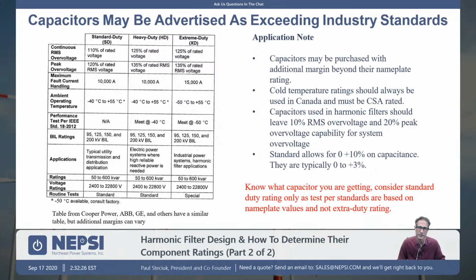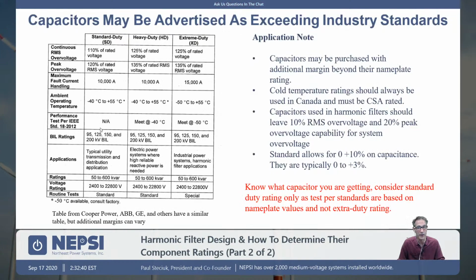Impulse rating, that's the impulse rating of your system. So if it's 13.8 kV, you're going to buy a capacitor that has a BIL rating of 95 typically. Now don't forget that you have altitude. You've got to worry about altitude when you're in the mountains above 1,000 meters. There's going to be a derating that you have to apply. And so typically we're specifying kVAR, voltage, and impulse rating, and the number of bushings is all that's required. So not a whole lot of things to specify there.